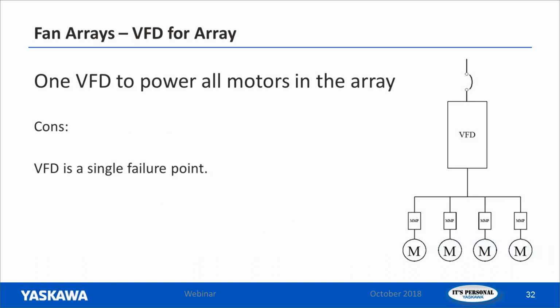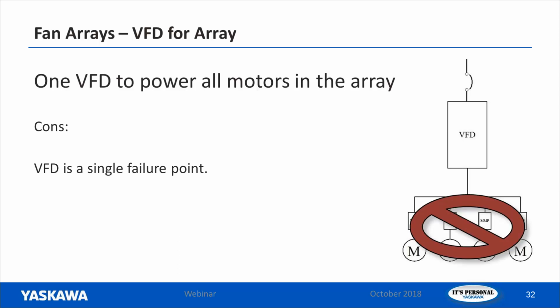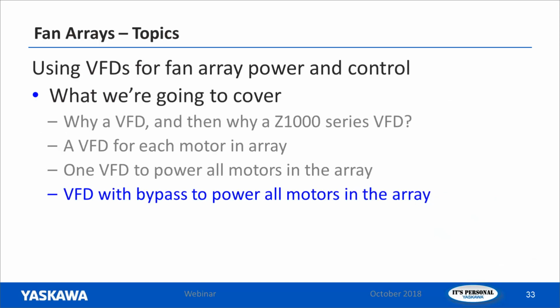Downside, in this configuration, we do have a point that would be considered a single failure point. Highly unlikely with a Z1000 drive, but schematically that's what it is. A VFD is a single failure point in this configuration. So if you do have an issue with the VFD, a fault or a failure of any kind, you have a potential of your entire array going down. So let's look at an option for that. How about a VFD with bypass to power all the motors in the array?